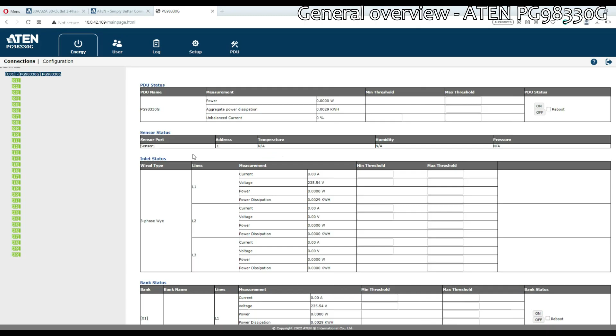Now let's enter the equipment with the new password. So this is the interface of our PDU. We have on the left side all our 30 ports. In the middle, an overview of the equipment and what it does. If we have sensors installed, they will appear here in the sensor part. Because we have a PDU that is both metered and switched, it means it will read the consumption data of each socket individually, and also give us the possibility to turn that socket on and off.